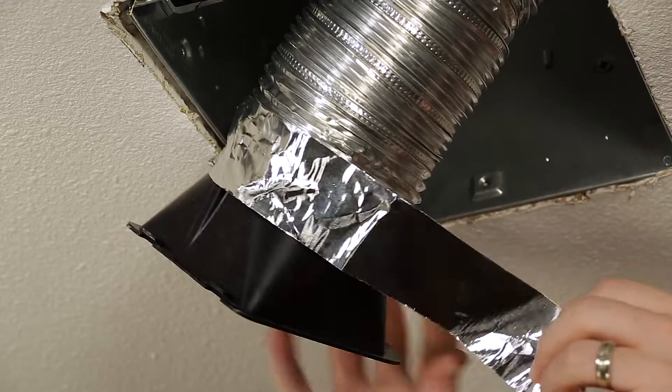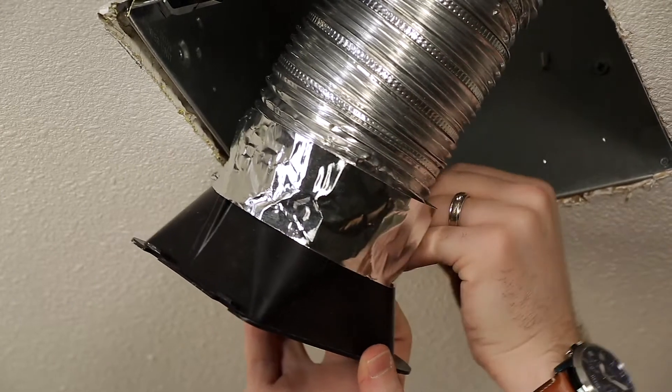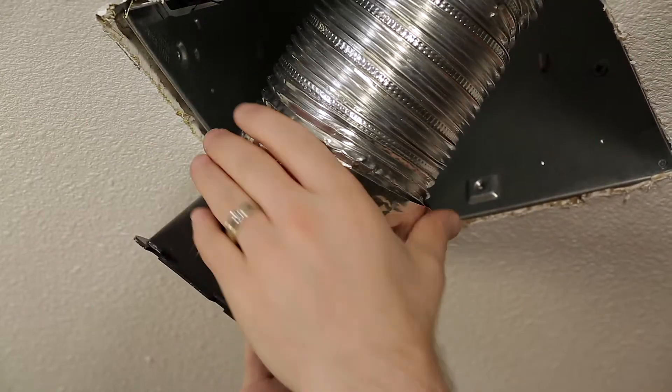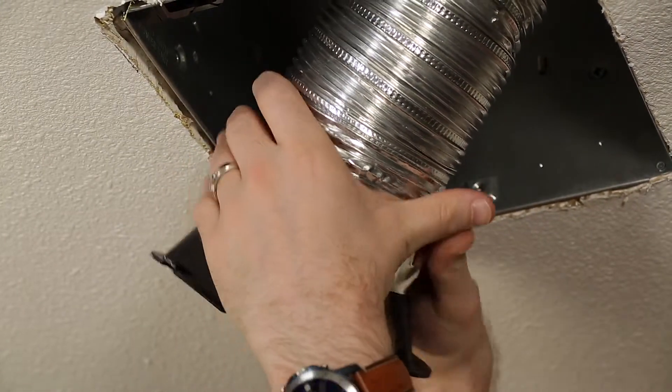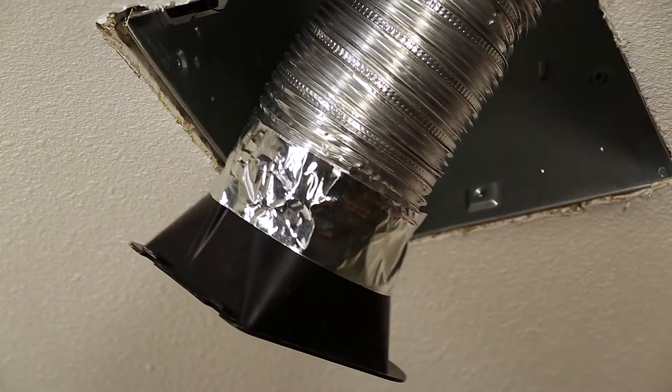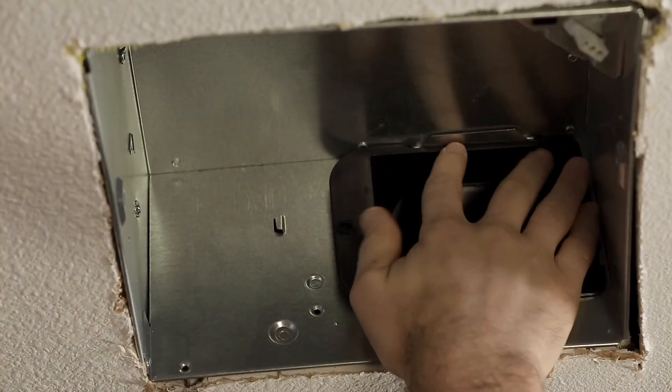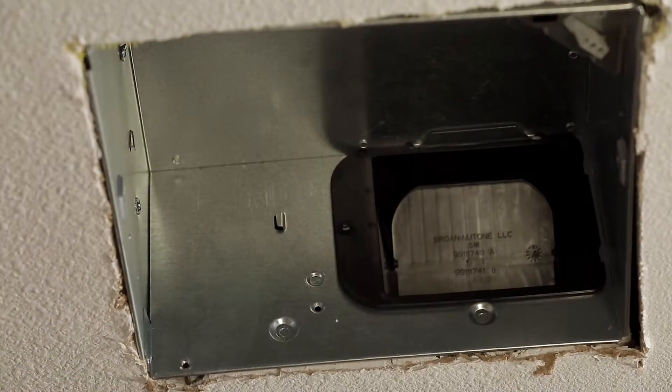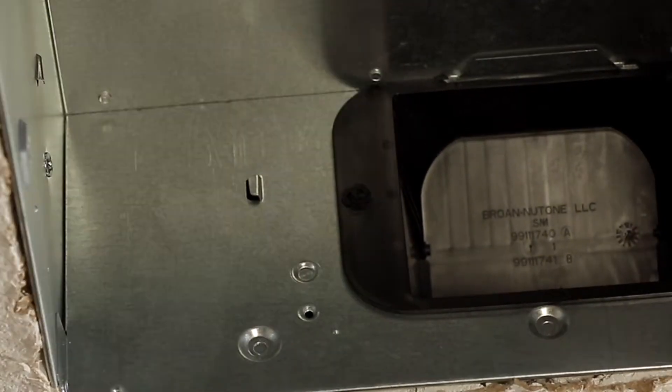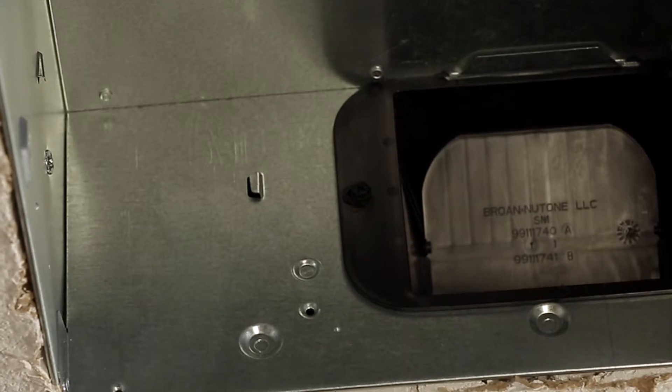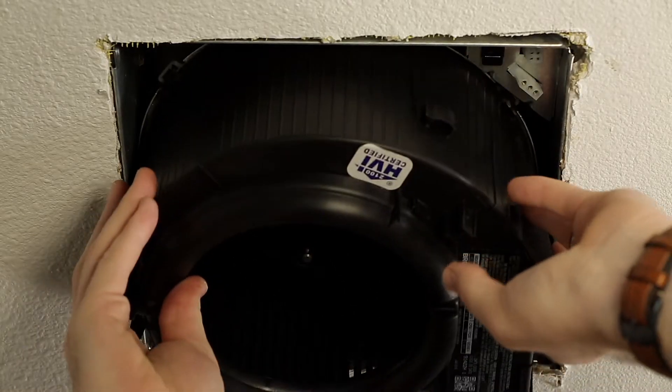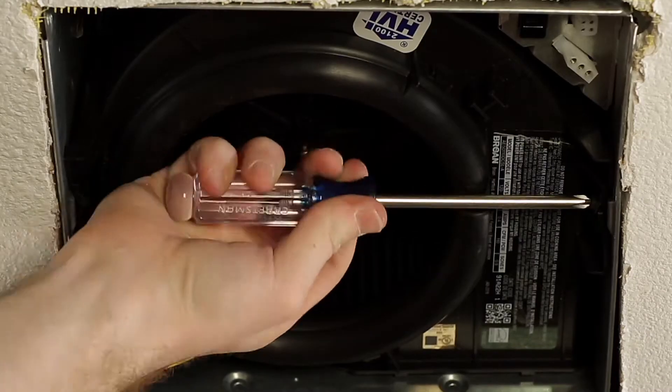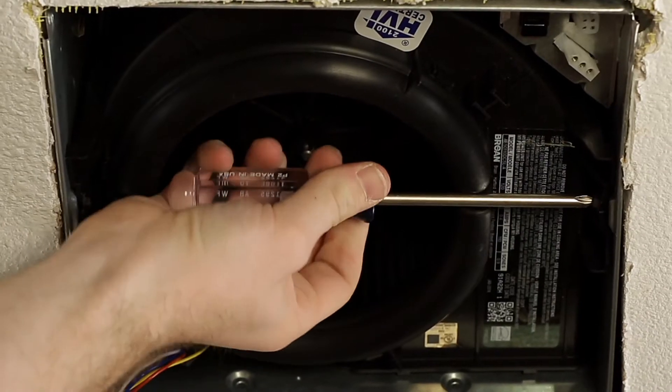Pull existing duct through the hole in the housing. Connect the duct to the duct connector with duct tape. Fit the duct connector into the housing, then engage the tabs and secure with the screw provided. Install the blower into the housing and secure it with two screws provided.